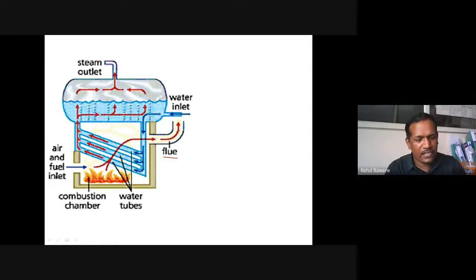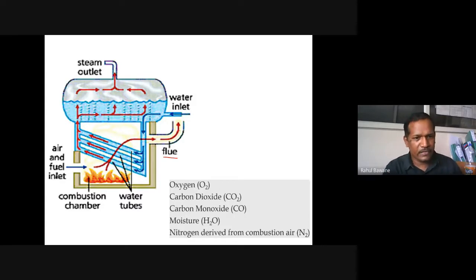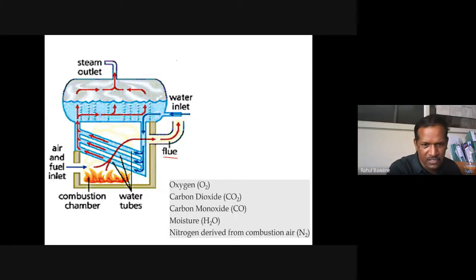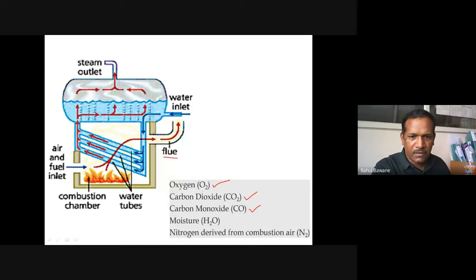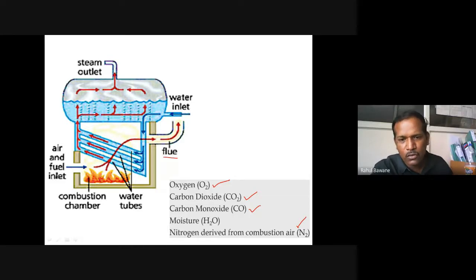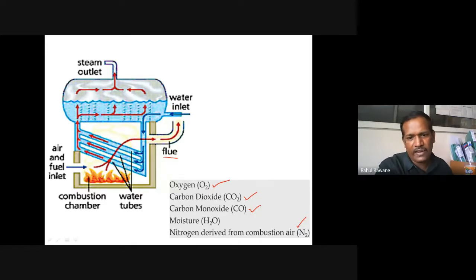We have to do the analysis of those flue gases. There are various instruments to analyze flue gases, but the simplest method is the Orsat apparatus. It is restricted to analyzing the content of oxygen, CO₂, and CO in your flue gas. By difference, we come to know how much N₂ is remaining. N₂ is not measured directly; it is the difference of total gas minus the sum of these three gases.